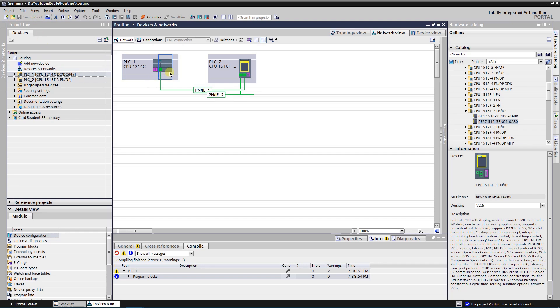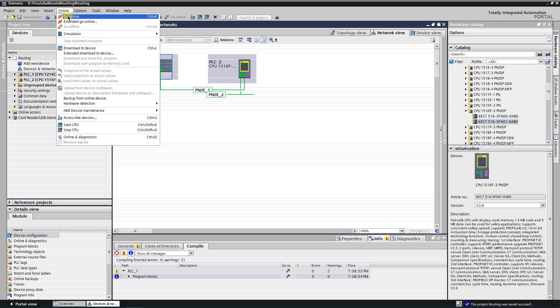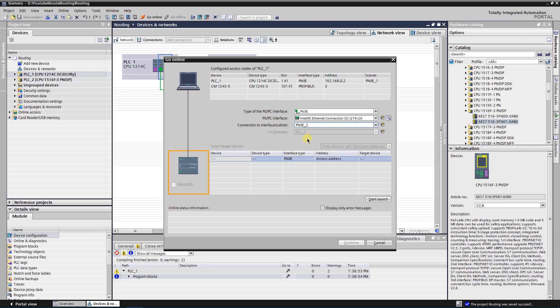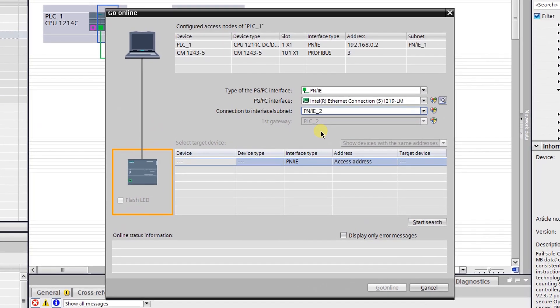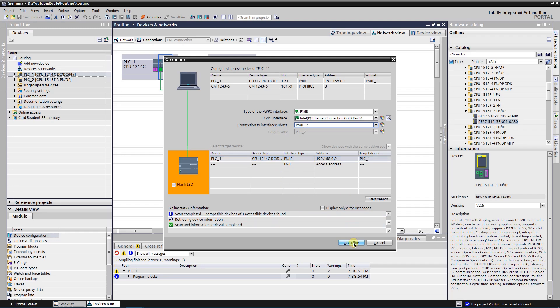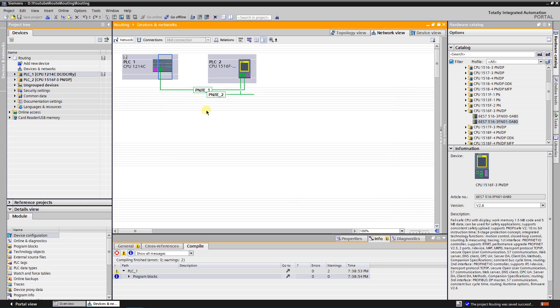After the process is finished, try to go online. Select your first CPU. Click on menu Online and select Go Online. Select PNIE2 as the interface subnet — it is where your PG/PC is connected. TIA Portal added the second PLC as a gateway automatically. Click on Start Search. The CPU has been found — click on Go Online. Connection to the first CPU is successfully established.